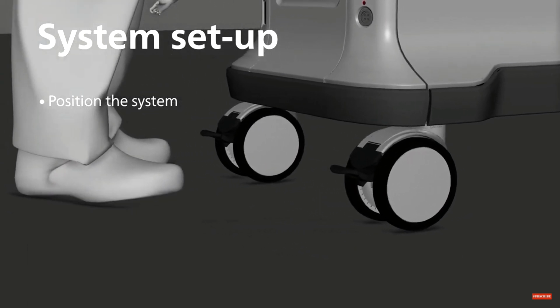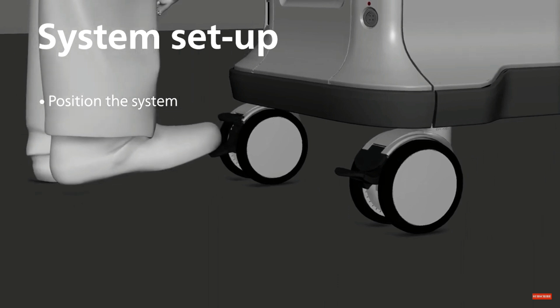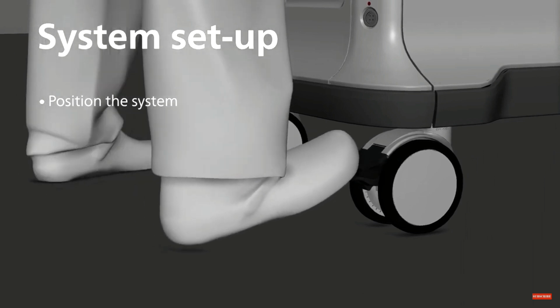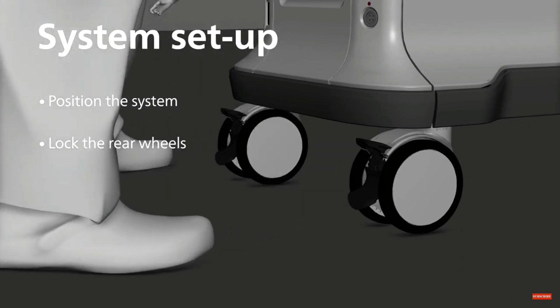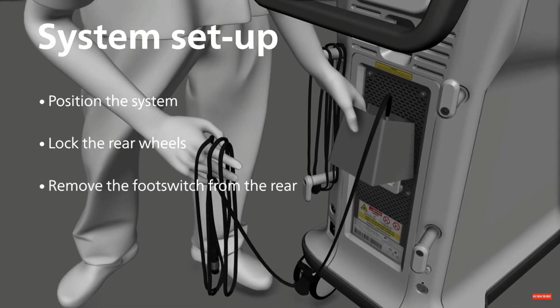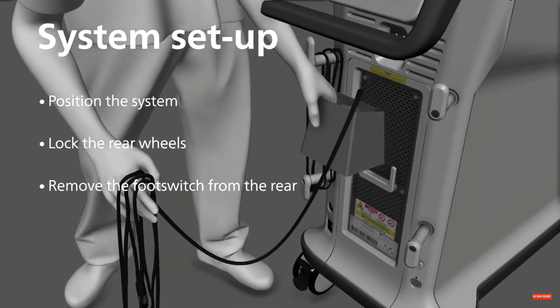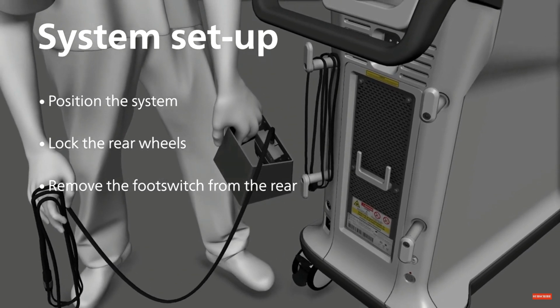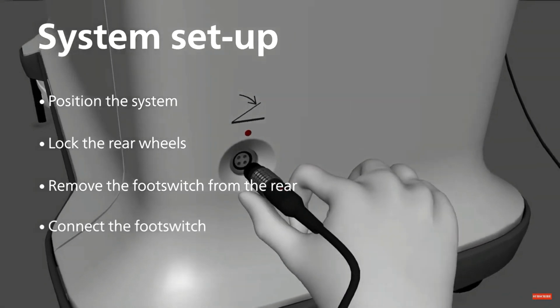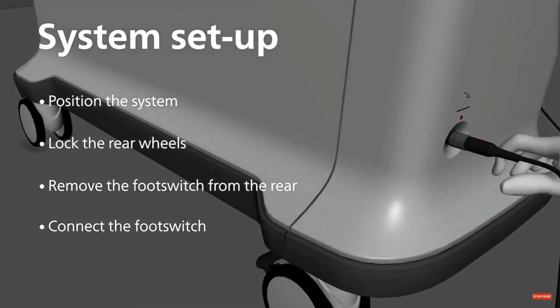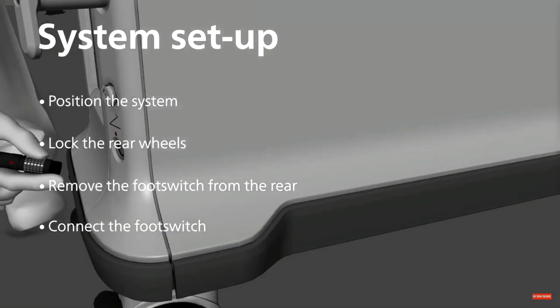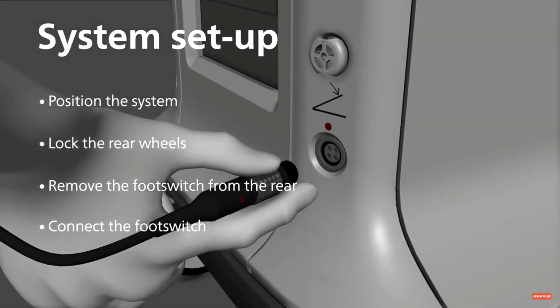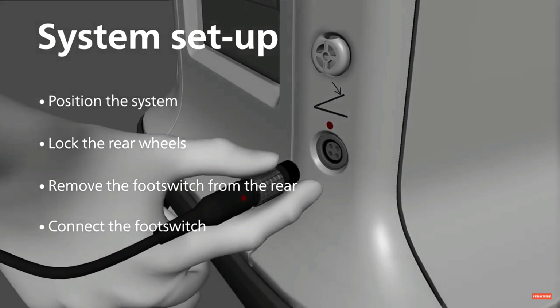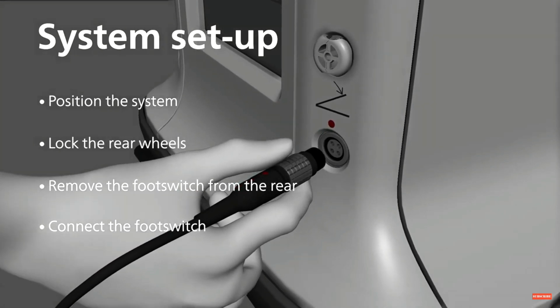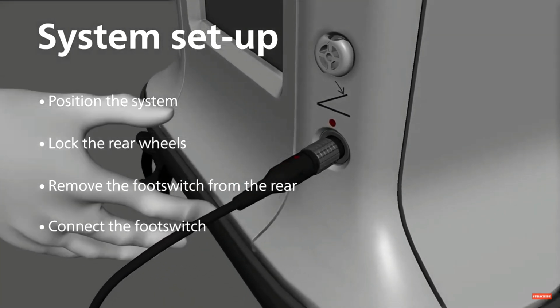The front wheels can be unlocked to allow lateral movement for final positioning. Rear wheels should be locked to avoid any movement of the unit once in position. Remove the foot switch and its lead from the storage location at the rear of the system. To connect the foot switch, align the red dot on the plug with the red dot on the socket. There is a socket for a foot switch on both the front and the rear of the system, but only one foot switch can be connected at a time.